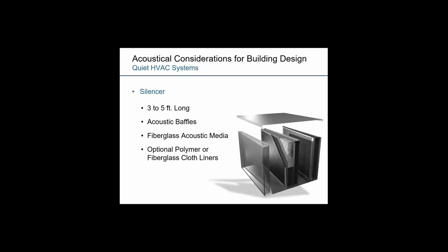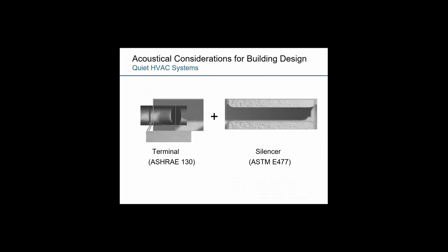And they have these internal acoustic baffles with acoustic media in that baffle. These often also have the option for a media protection, like I mentioned earlier, a polymer film lining or a fiberglass cloth lining to help prevent any exposure of that media to the airstream. And the reason for this type of development and solution is that terminal units and silencers are tested to two very different standards. In general, terminal units are tested to an ASHRAE 130 standard for airflow and sound, whereas silencers are tested to a different ASTM E477 standard.